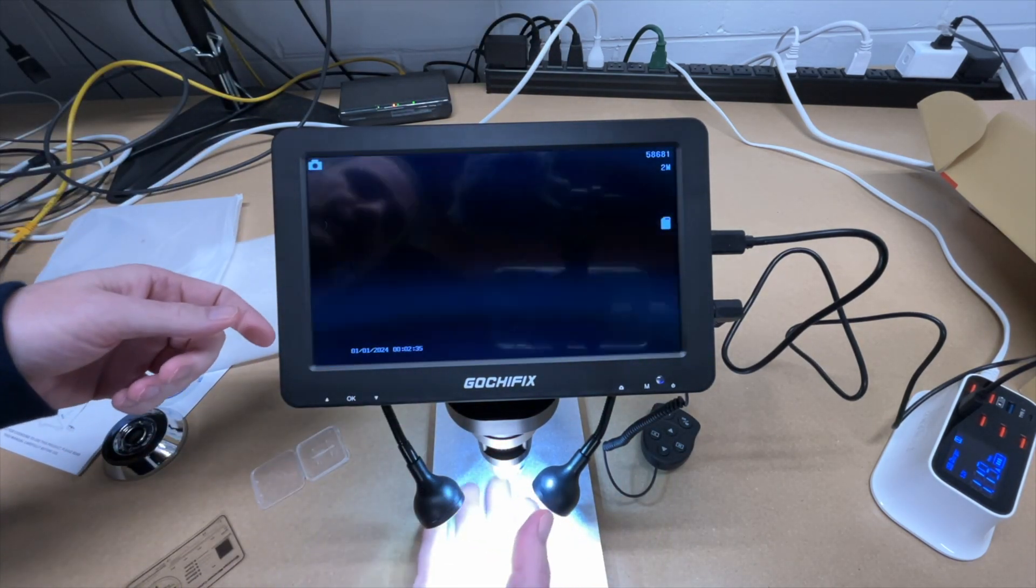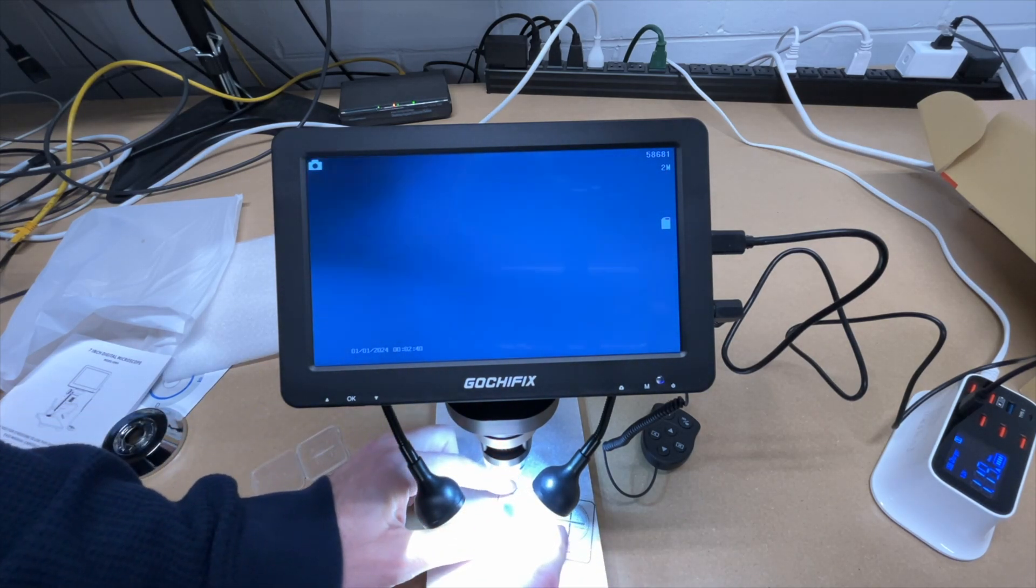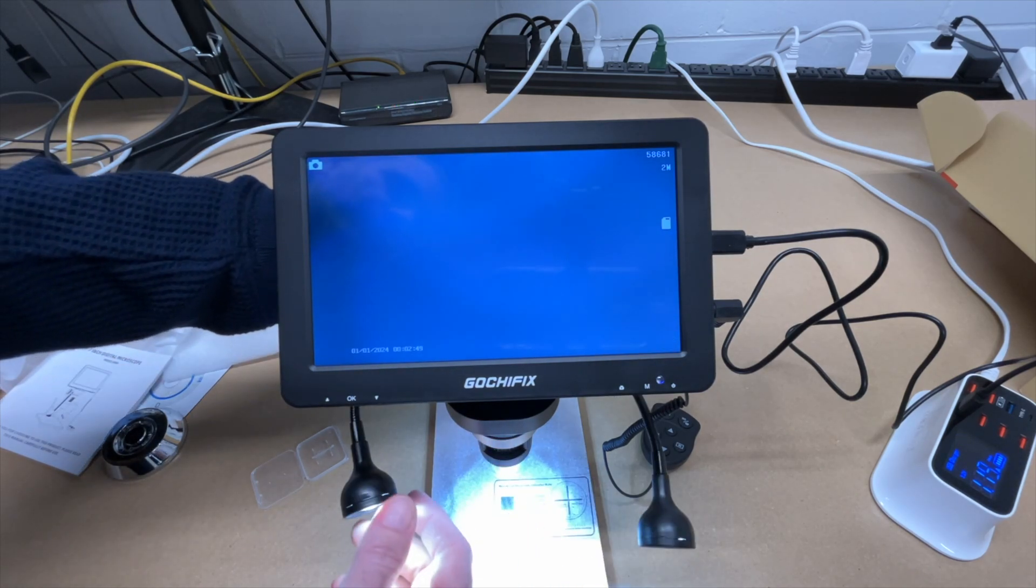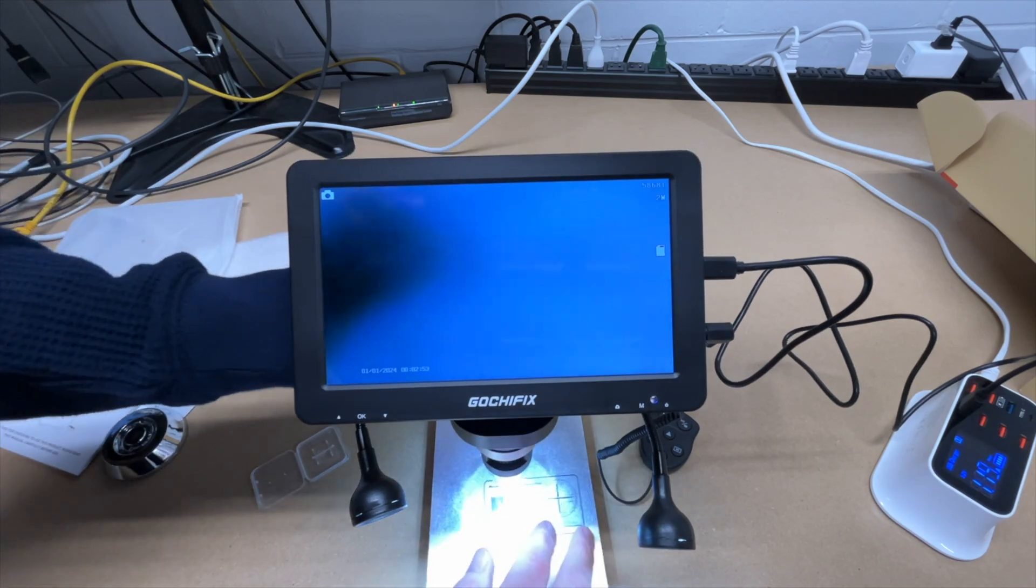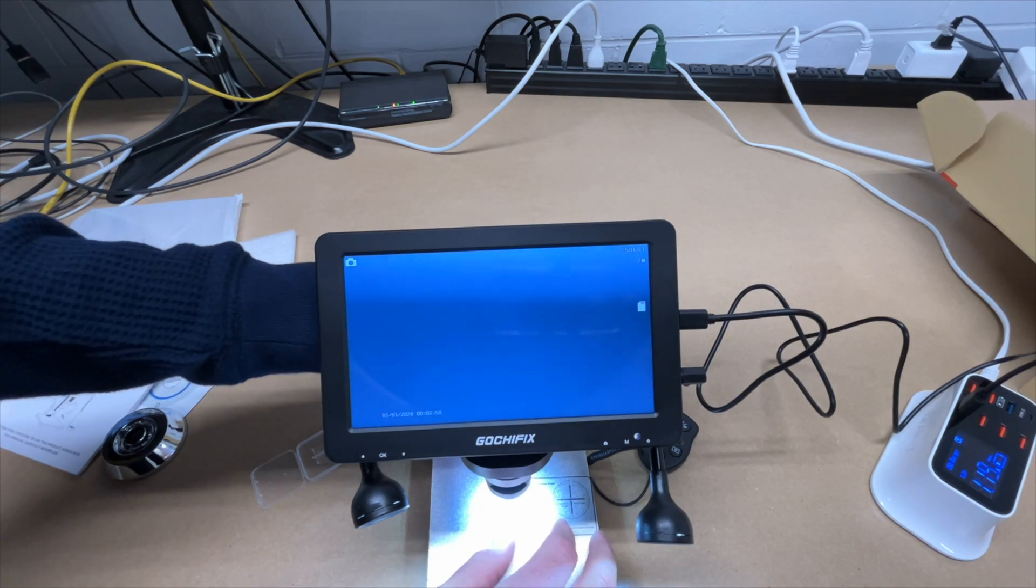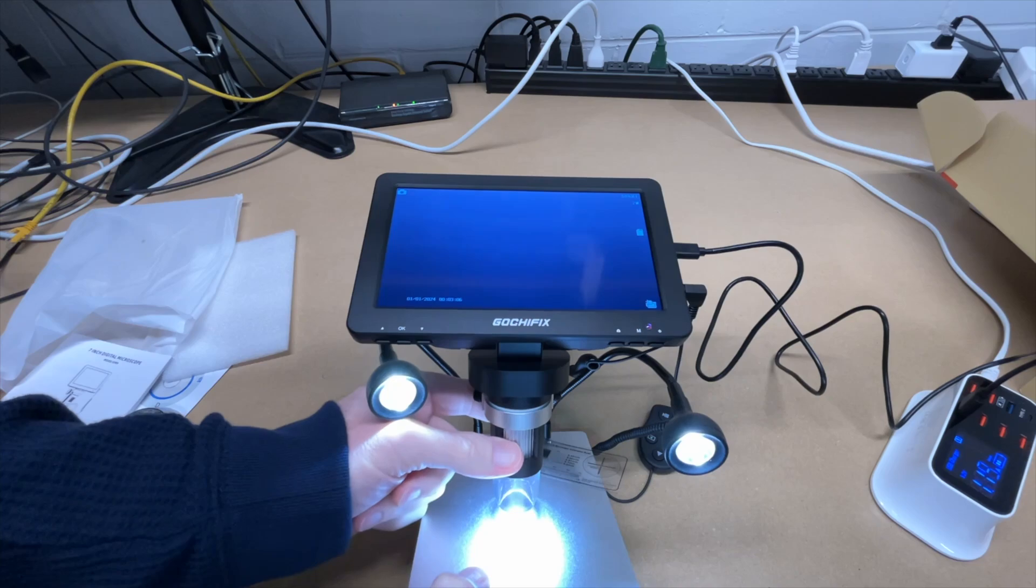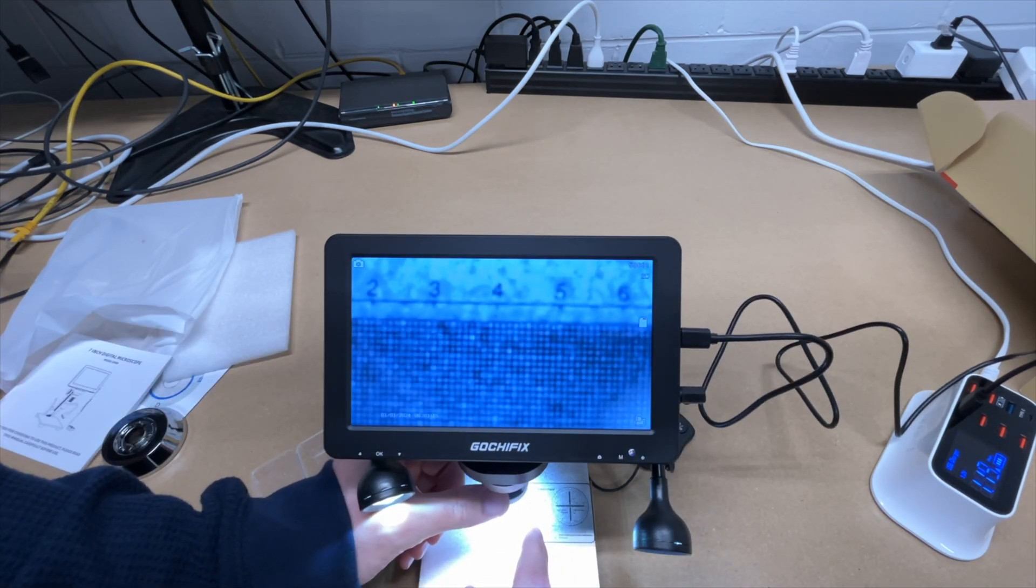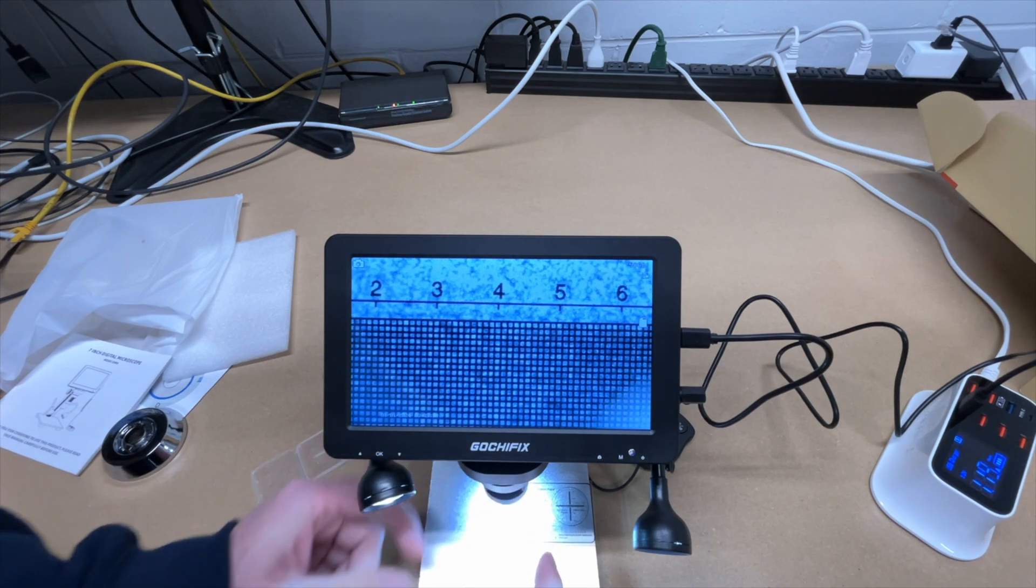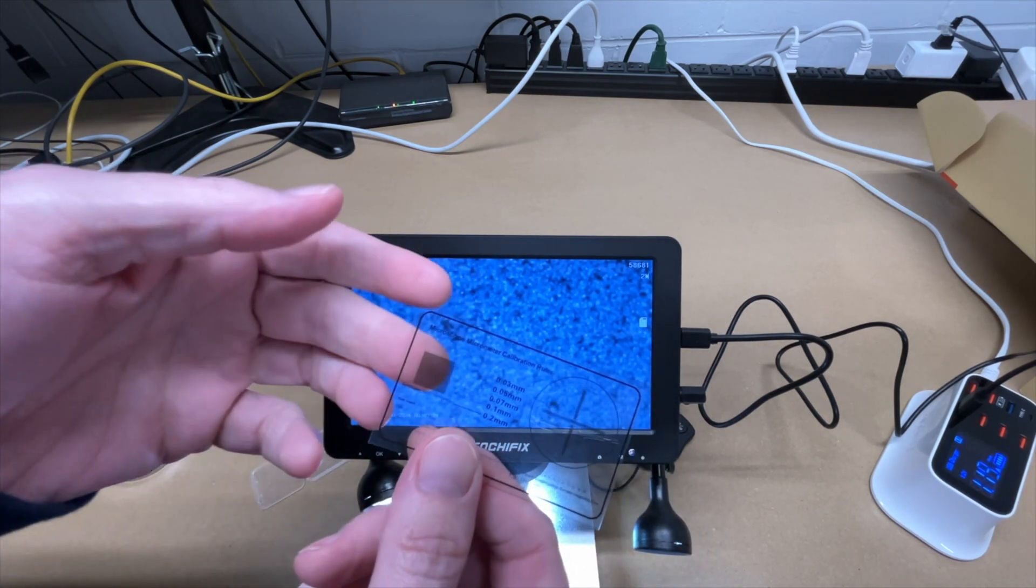So let's just go back to picture mode. And it may not look like much here, but it's not focused. So let's just start with this calibration thing. So I'll set this down. So now I'm going to lower the microscope. I'll loosen that nut up on the back and I'll lower it. I'll just go right about there. So I'm going to tighten that down. And now I'm going to rotate this to focus it. Now this is going to be very sensitive.